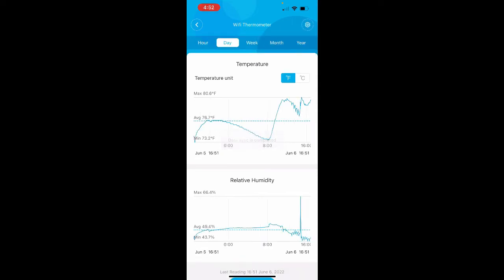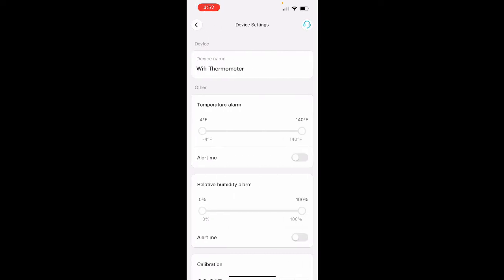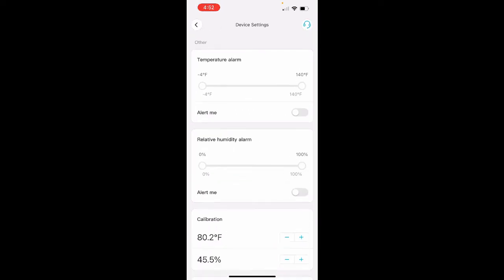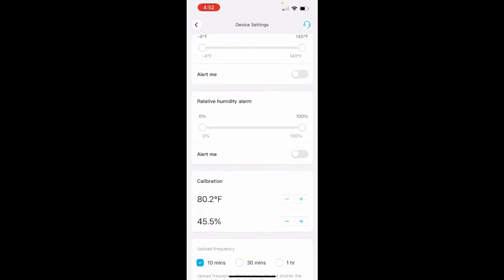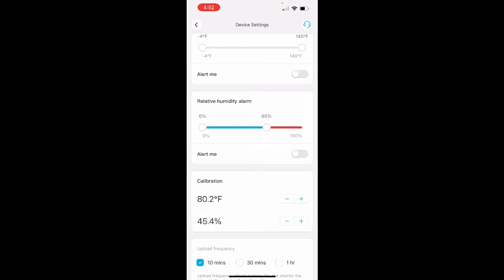At the top right of this screen, there's a gear that will take you to the settings. If you scroll down settings to relative humidity alarm, we want to pull the slider left from 100 down to 65%. Once we're at 65%, click on alert me.